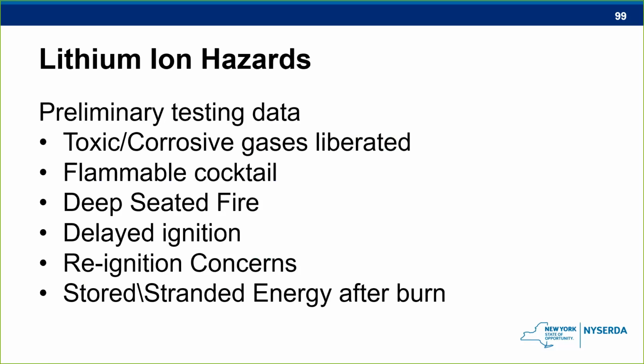Also, there's deep-seated fires. So if a firefighter were to pull up to the scene and they were taking their thermal imaging camera that they use quite frequently to look for heat sources, some of these heat sources may be too deep inside the cabinet or in the module itself for them to see. So they may not be able to see it. Probably there's a good chance they won't see it, and that's not a bad thing. We really don't want the firefighters going in there right away. As a matter of fact, we'd like to keep them out as much as possible, and we're going to explain later on how we're going to do that.